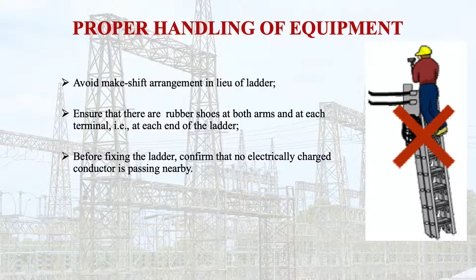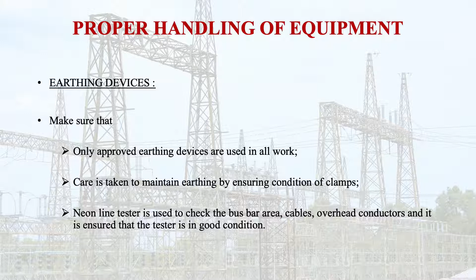Now let us discuss some precautions for earthing devices. Make sure that only approved earthing devices are used in all work. Care is taken to maintain earthing by ensuring the condition of clamps where the earthing is connected. A neon line tester is used to check the bus bar area, cables, and overhead conductors, and it is ensured that the tester is in good condition when working on the electric system.